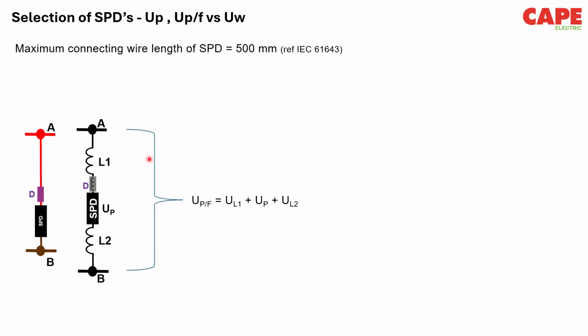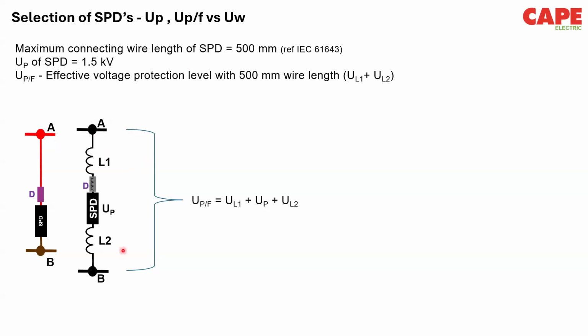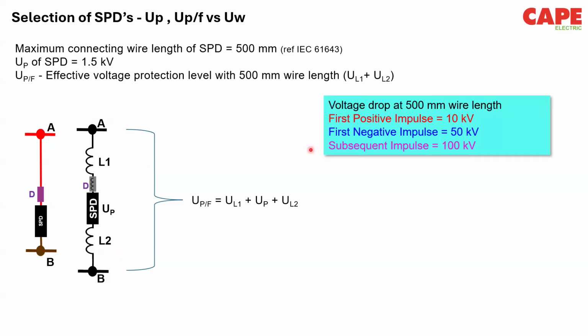Now, if I take a connection lead length of 500 mm or 50 centimeter, that means L1 plus L2 is 50 centimeter, and UP of the SPD is 1.5 kV. And for UPF, as I've already told you, you have to add all these together. For a level 1 lightning, that is 200 kA, the voltage drop at a 500 mm wire length for a first positive impulse is going to be 10 kV. First negative impulse is going to be 50 kV, and subsequent impulse is going to be 100 kV. Okay, all those calculations you can also refer to in part 1 of the standard, where they have a beautiful table.